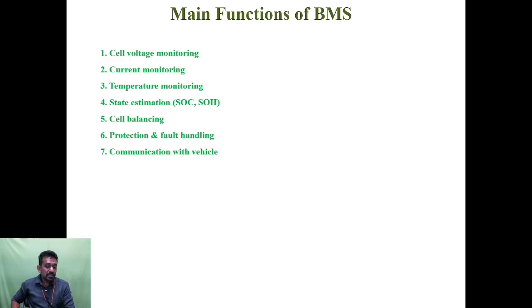Next is cell balancing. Each and every cell, even if made by the same manufacturer, has different physical, chemical and thermal conditions. One will have a high level of voltage charging, another a low level. To balance and remove this uncertainty between cells, we need the aid of the battery management system, which balances each and every cell under different conditions.